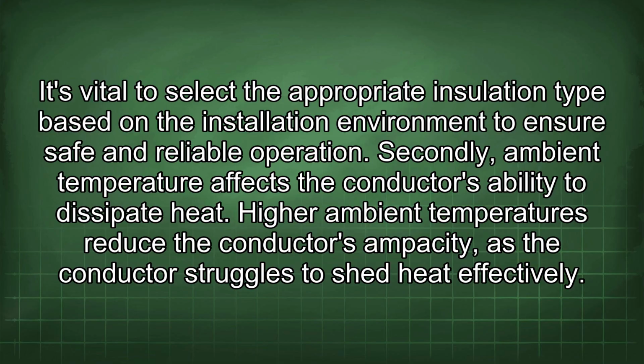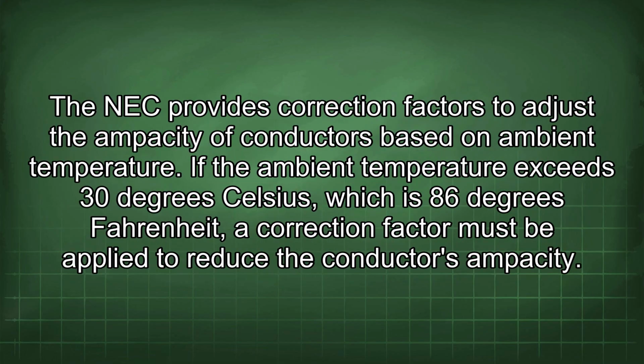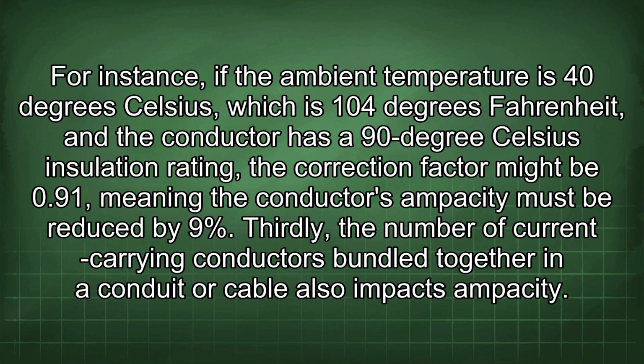Secondly, ambient temperature affects the conductor's ability to dissipate heat. Higher ambient temperatures reduce the conductor's ampacity as the conductor struggles to shed heat effectively. The NEC provides correction factors to adjust the ampacity of conductors based on ambient temperature. If the ambient temperature exceeds 30 degrees Celsius, which is 86 degrees Fahrenheit, a correction factor must be applied to reduce the conductor's ampacity. For instance, if the ambient temperature is 40 degrees Celsius, which is 104 degrees Fahrenheit, and the conductor has a 90 degrees Celsius insulation rating, the correction factor might be 0.91, meaning the conductor's ampacity must be reduced by 9%.